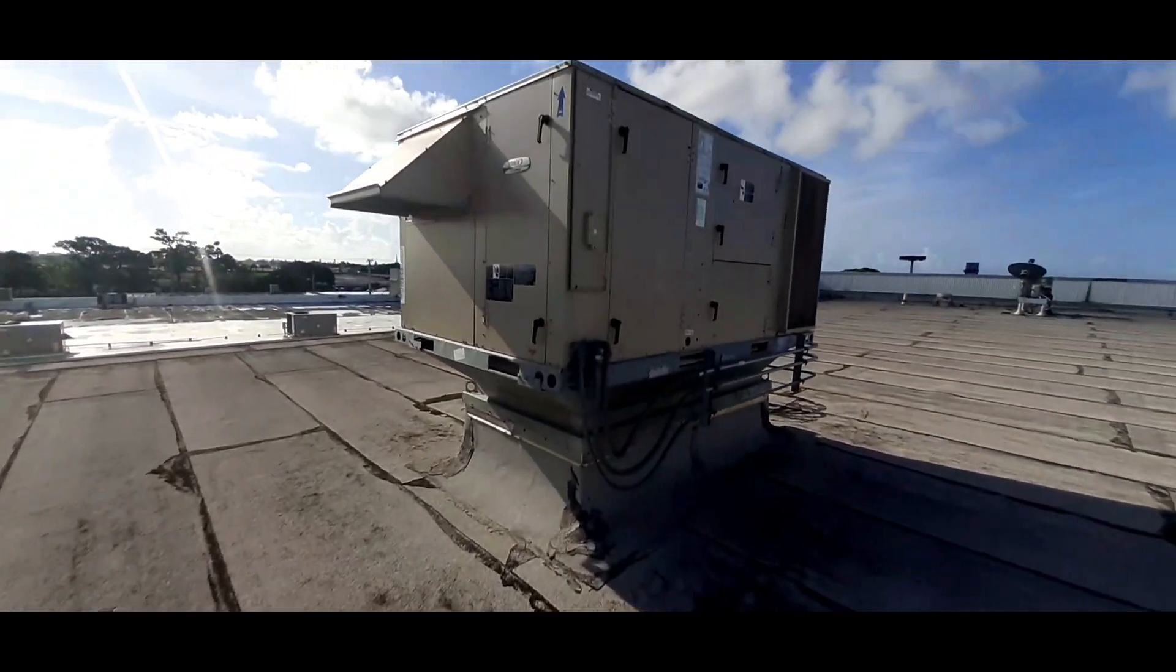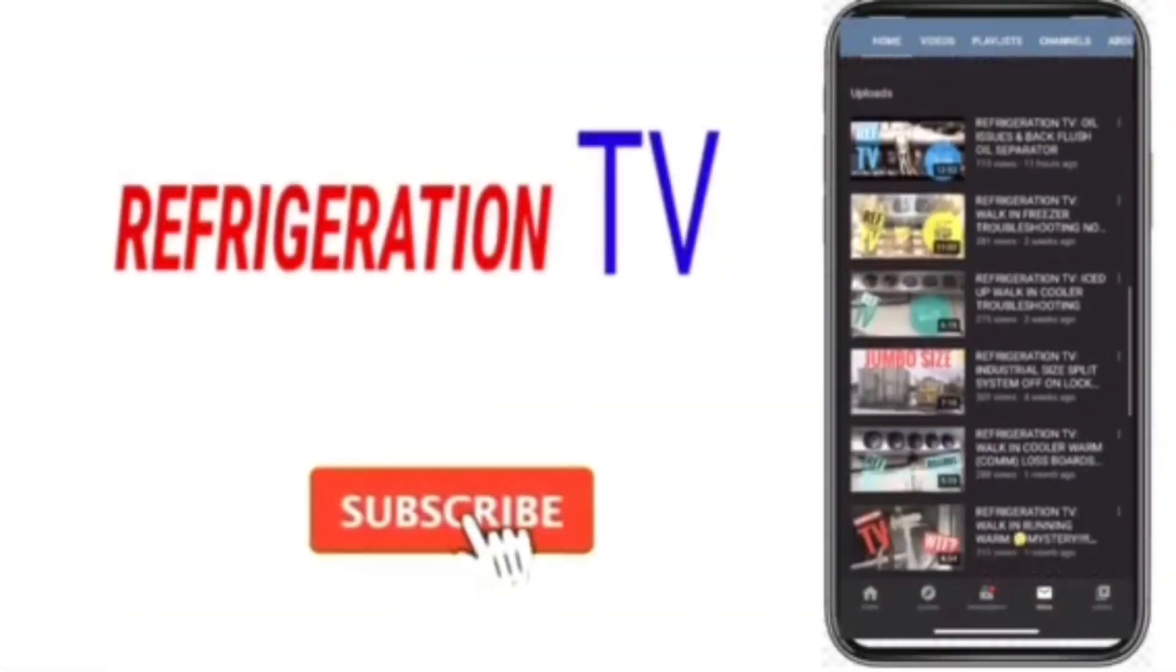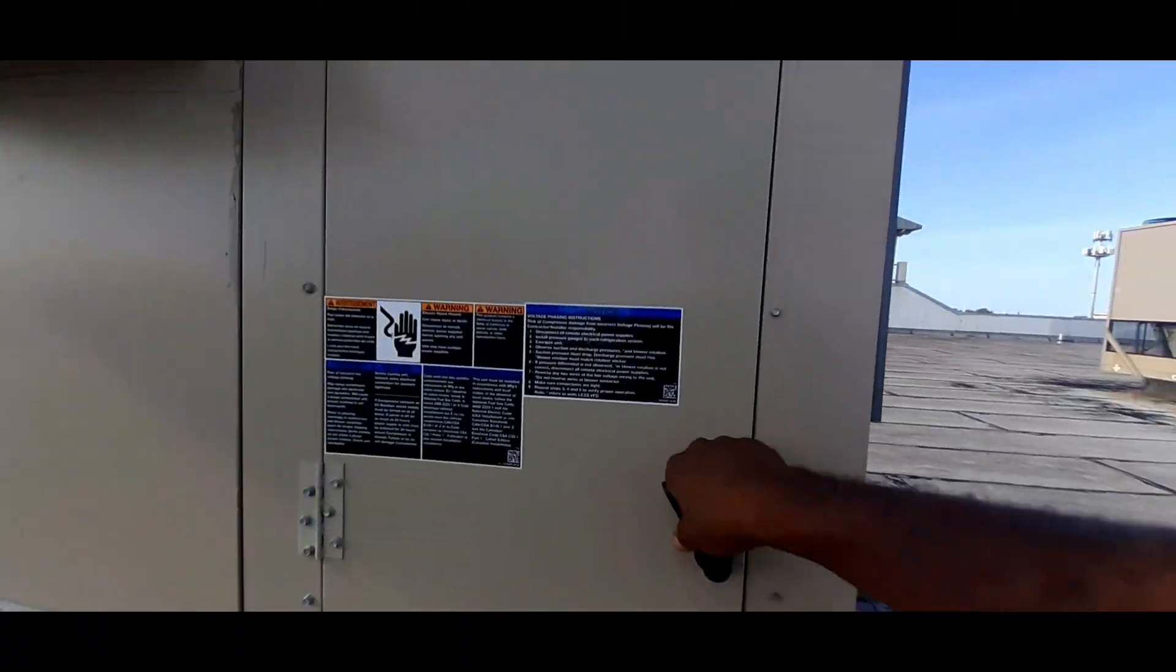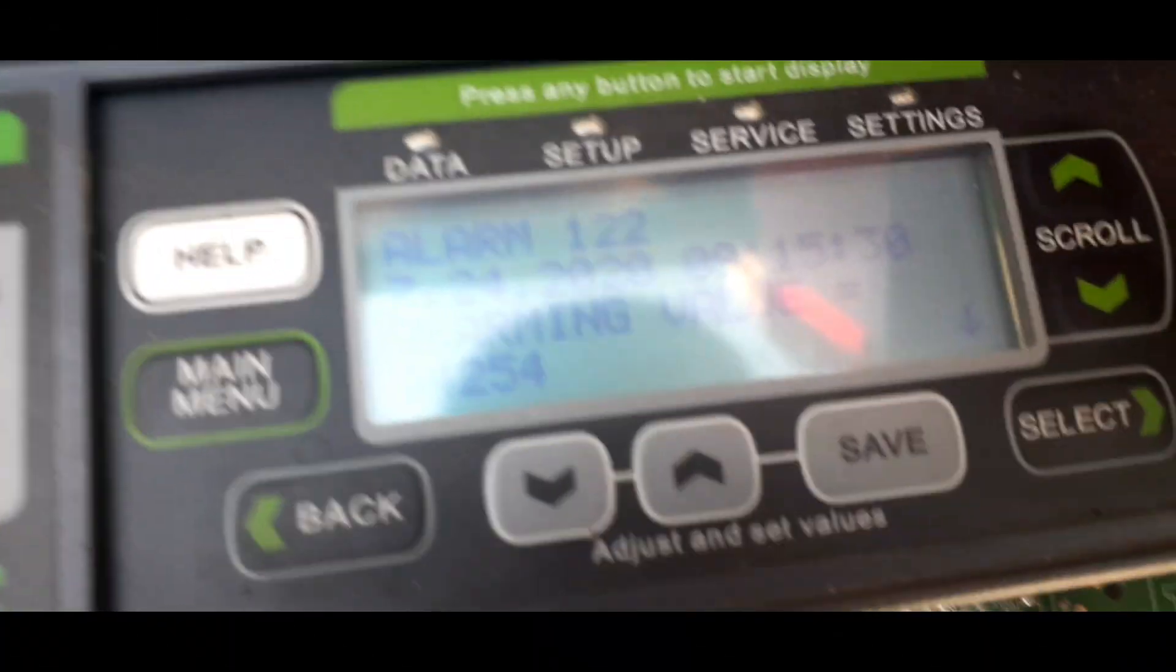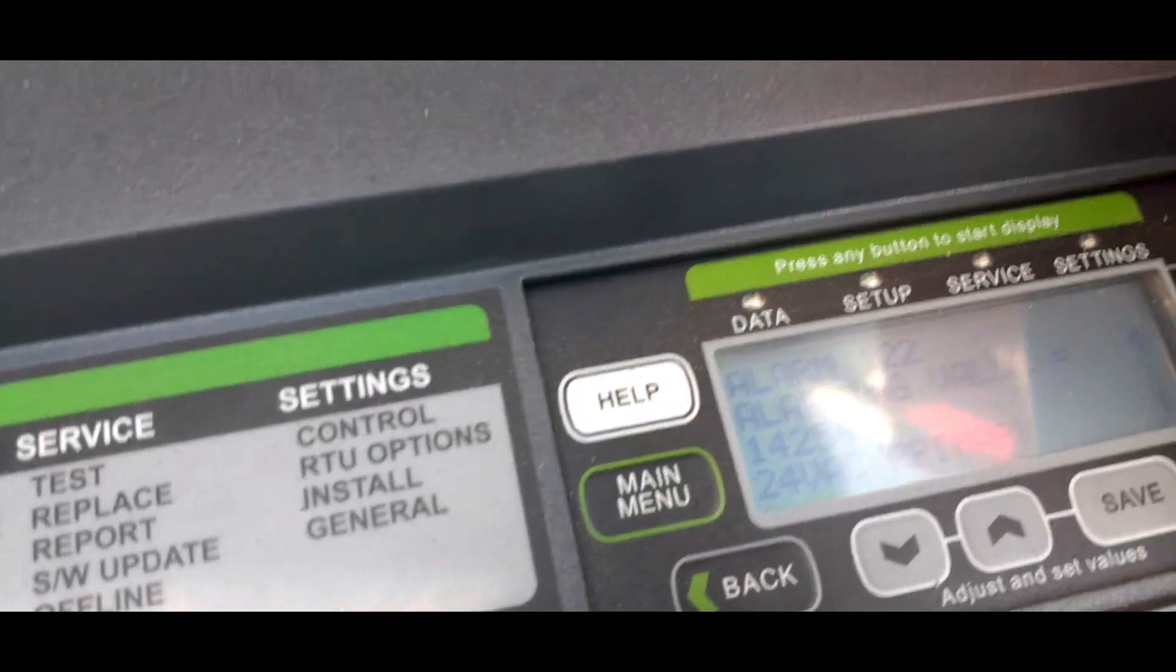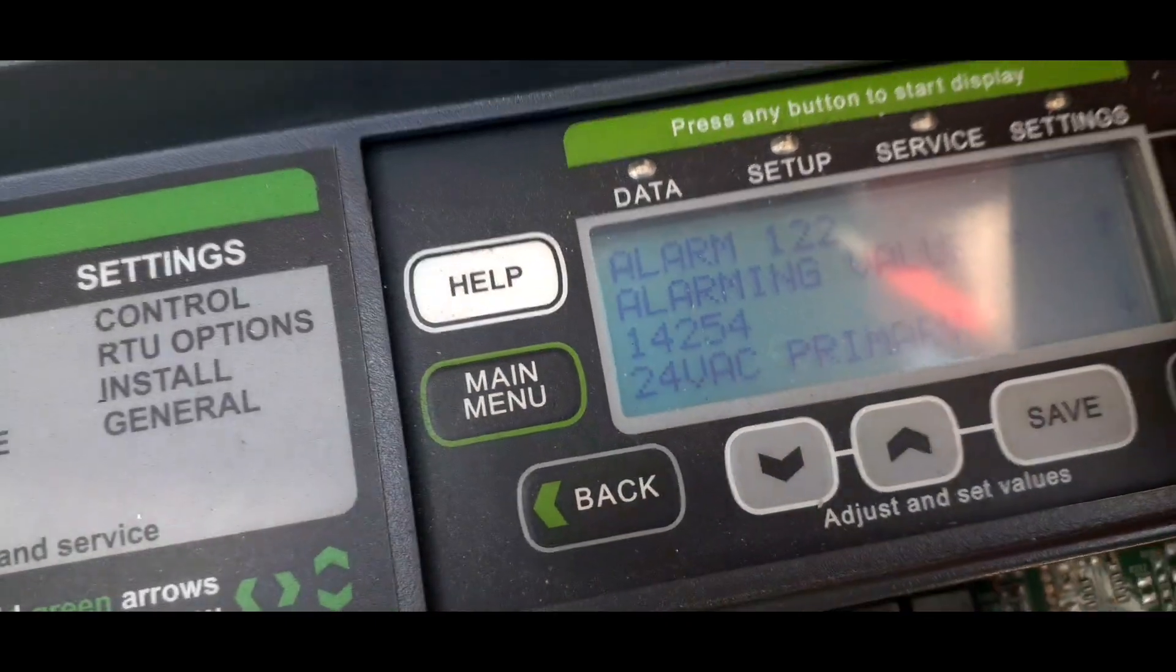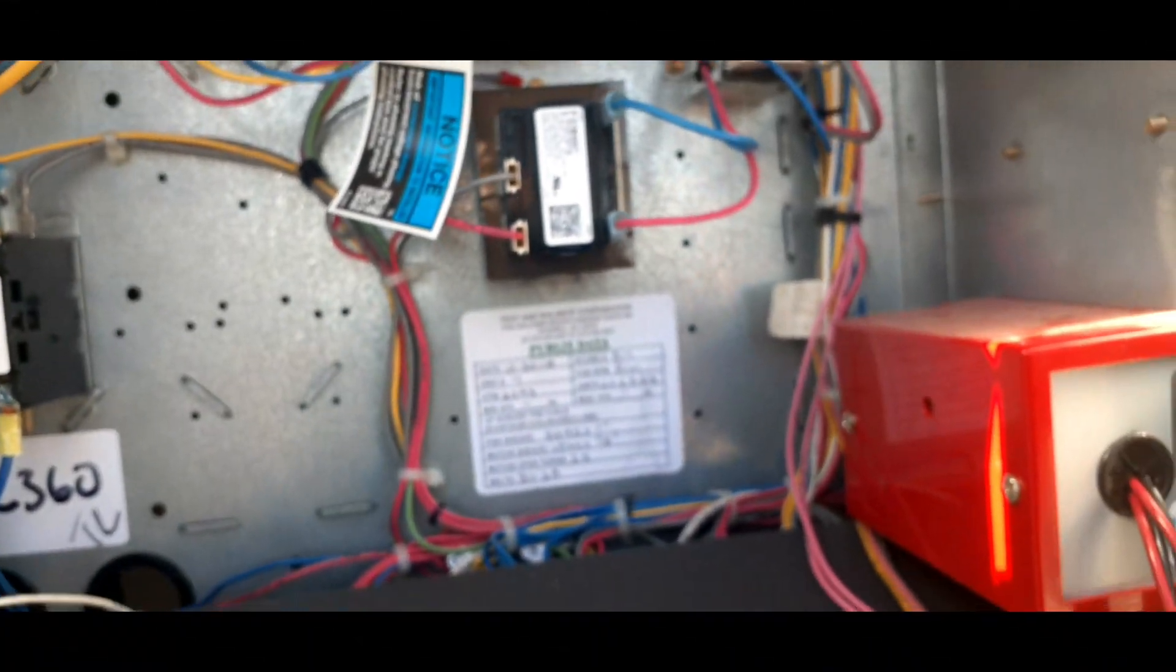All right, so we got a service call. I got a Lennox unit that's not cooling. So far sounds like it's not running, nothing's running. Open this up, my controller right here. All right, so let's see what we got here. What's that? Alarm 122. Scroll down, alarm value 14254, 24 volts primary. So it says that we don't have 24 volts, the voltage is low. We got two transformers up here.